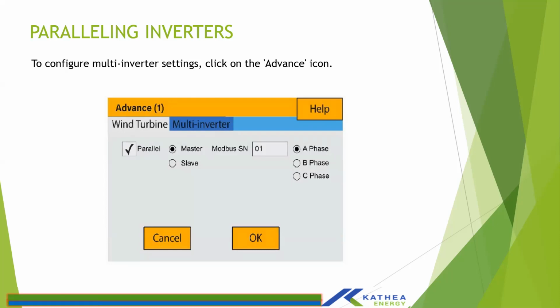Then for the specific inverter, you would need to activate that it's connected in parallel, whether it's a master or slave, and then you would need to set the Modbus ID, which is the Modbus serial number SN. For each inverter connected in parallel, it has to have a distinct ID. So it means all the Modbus IDs have to be different for all the inverters connected in parallel. And then you would need to select which phase the inverter is connected to, right?